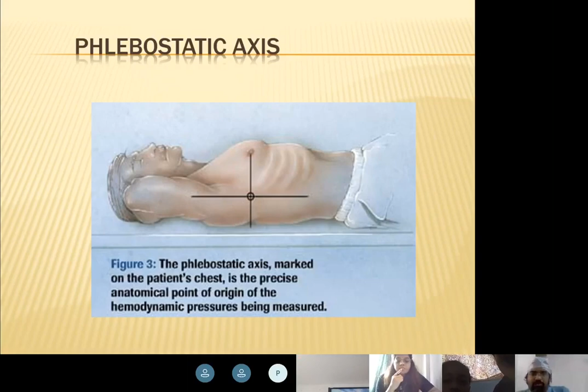Now, what happens when you move the patient up? If the transducer is attached to the patient, there is no problem, and the transducer remains the same. If you keep your transducer on a pole and then you move the patient up, that will be a problem, because the transducer will not move with the patient. The transducer will remain down and the patient will go up. If that occurs, then your pressures will change. Am I clear on this?